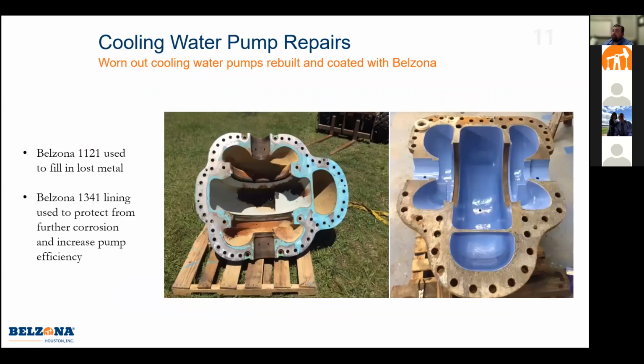Now we'll switch gears to the cooling water pumps that feed and supply cooling towers and extract from them. This is one of the top ends of a water pump we've done that comes right off a cooling tower. We used our Belzona paste to fill in all the damaged areas where you can see the previous coating failed and caused a lot of corrosion and pitting.